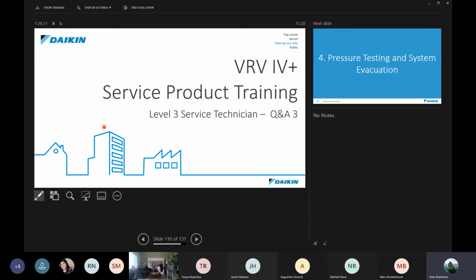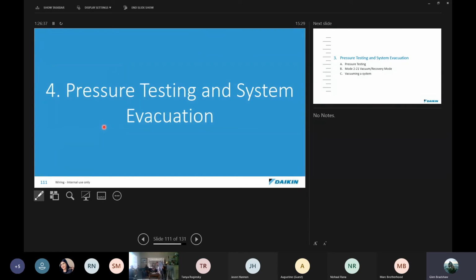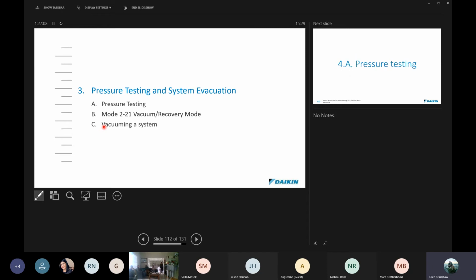All right. So we're going to go on to the next section, and this I'm just going to touch on this week. We're going to look at pressure testing and evacuation of the system. After you've done the piping and everything, you need to do a pressure test, and then system evacuation. This is often where we pick up some of the biggest problems. Let's go through the pressure testing. We're going to look at mode 21, vacuum recovery mode. It's a very important mode to know when working with VRV, and it can be used for solving a lot of problems, and then vacuuming a system.